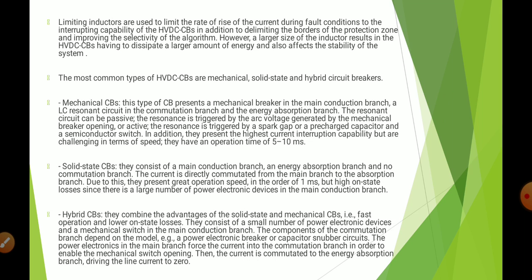Hybrid circuit breakers. They combine the advantages of the solid state and the mechanical circuit breakers: fast operation and lower on-state losses. It consists of a very small number of power electronic devices and a mechanical switch in the main conduction branch. The components of the commutation branch depend on the model, for example a power electronic breaker or capacitor snubber circuits. The power electronics in the main branch force the current into the commutation branch in order to enable the mechanical switch opening. Then the current is commutated to the energy absorption branch, driving the line current to zero.